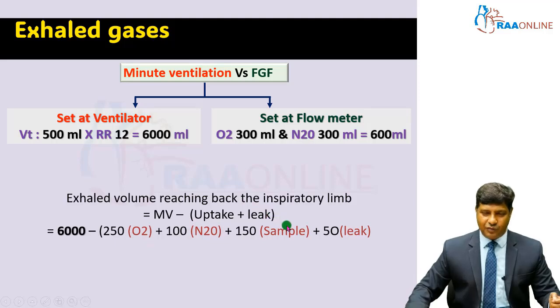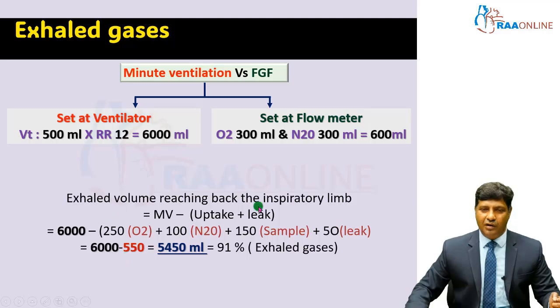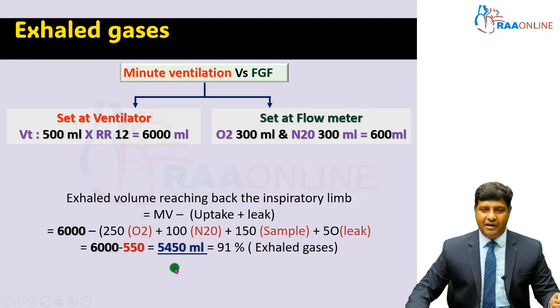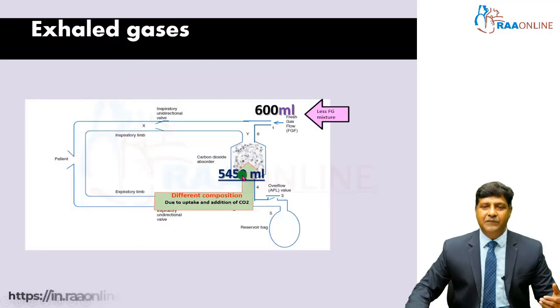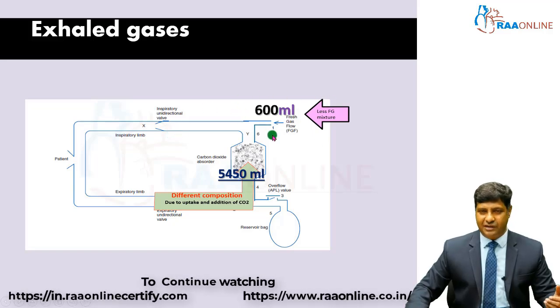For ETCO2 sampling, if you do not have a method to reintroduce the sampling gas back into the system, assuming the sampling loss is about 150 ml and a leak of about 50 ml, the total loss is 550 ml, which is taken away from the minute volume. So, 6000 minus 550 equals 5450 ml — this is the amount that enters the patient's inspiratory limb again. If the minute ventilation is about 6 liters, the fresh gas flow we set is going to be around 600 ml.